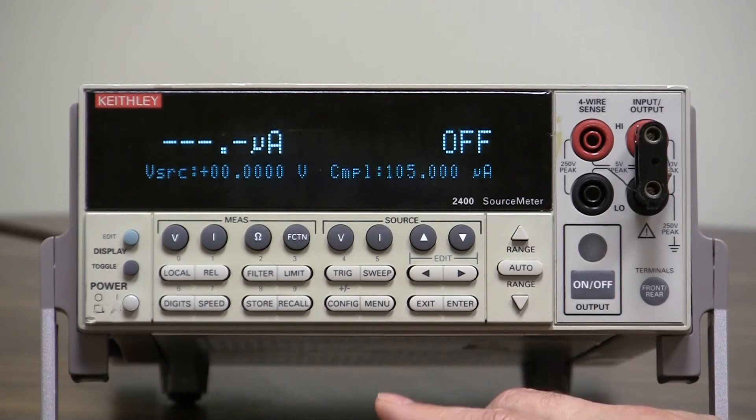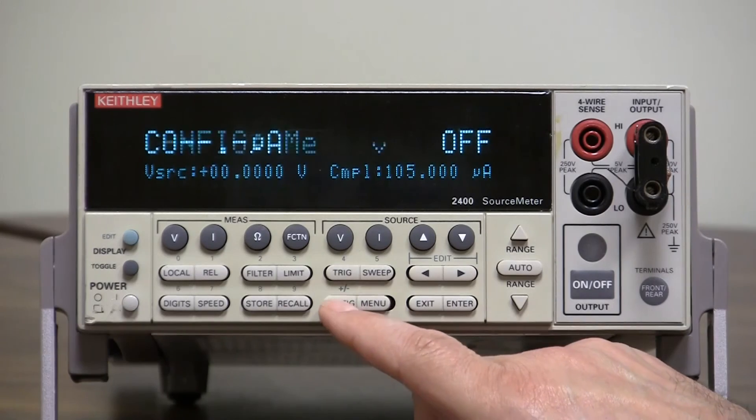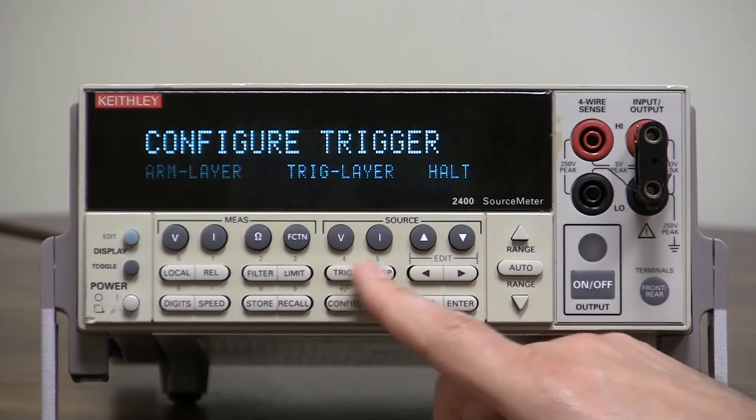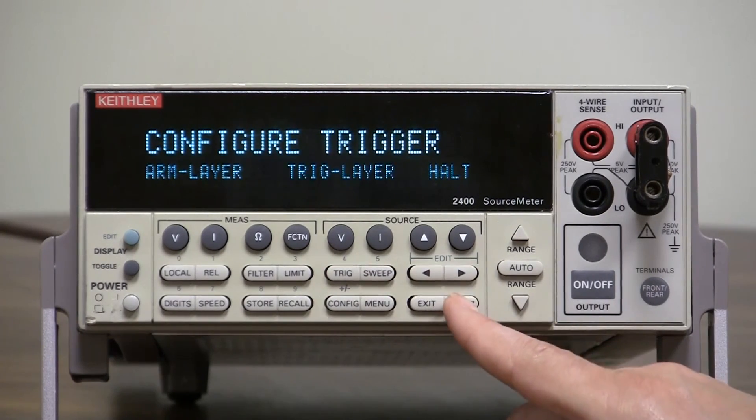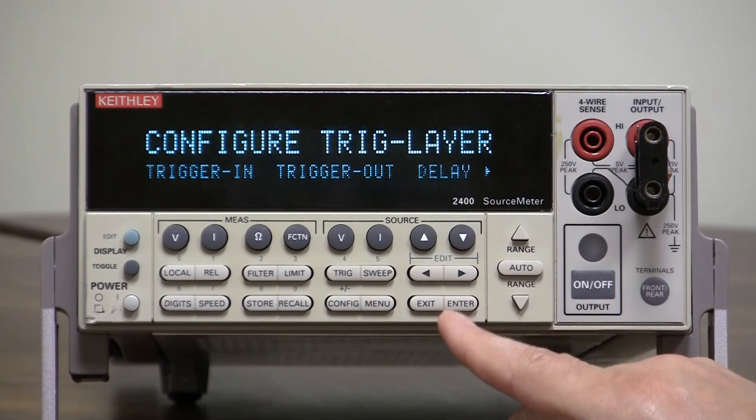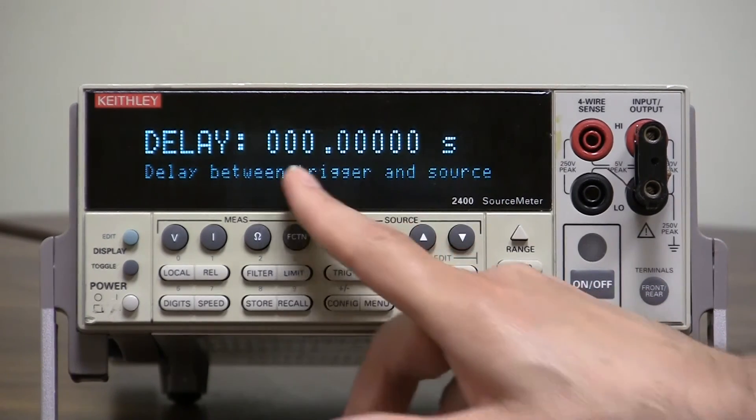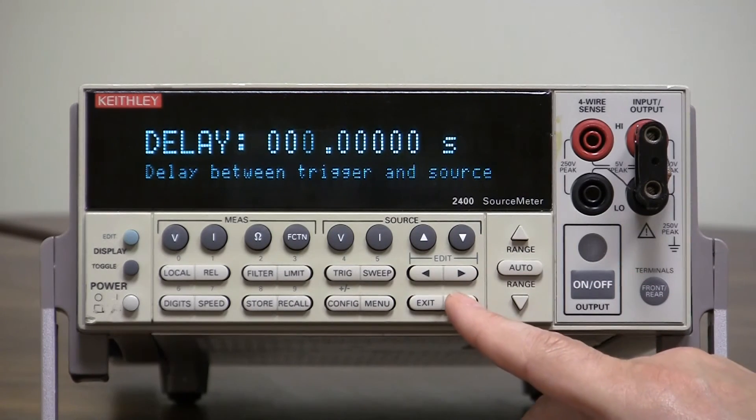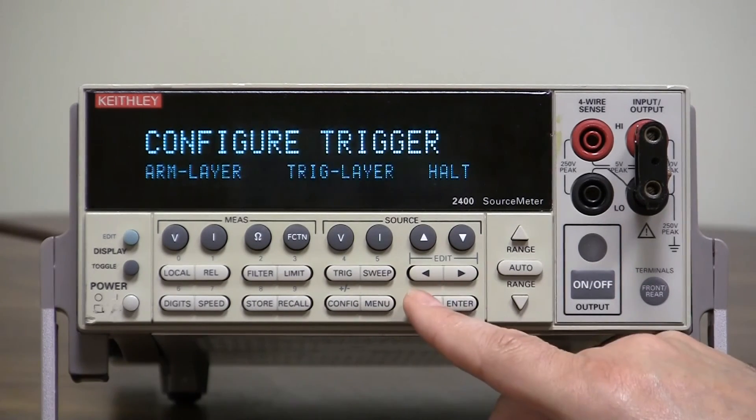And we need to set up the trigger delay. Configure trigger, go to the trigger layer. You'll see delay, enter. That's already set to zero. It's good to check. Enter, exit, exit.